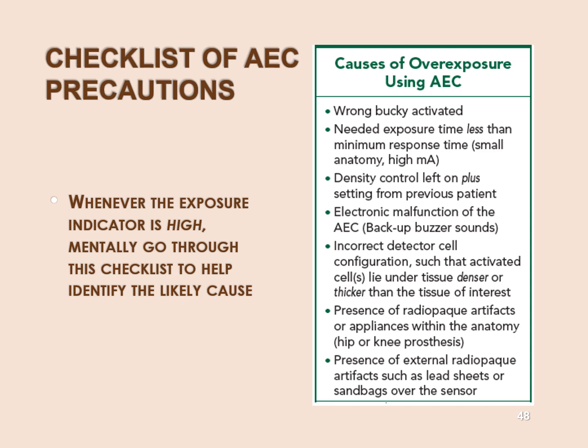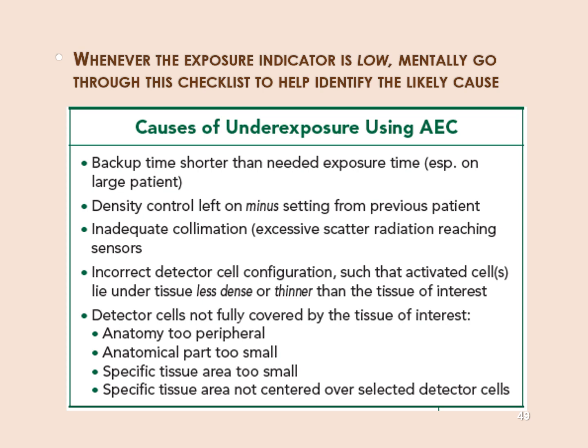Lead shields, lead sheets, or sandbags in the exposure field over the chamber will also make the exposure run long. Remember, we're counting radiation. We count radiation by counting ionizations, turning them into stored charges. We are not actually using any timing device in an AEC.